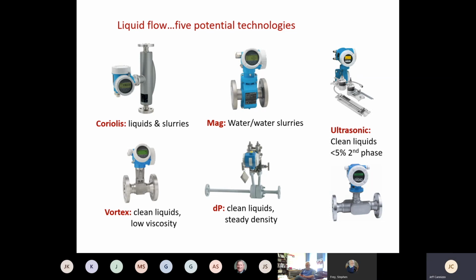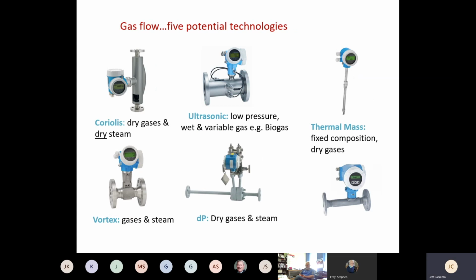Endress+Hauser does not manufacture the primary flow elements. Most of the representatives have relationships with other manufacturers. We have a relationship with Wyatt Engineering for orifice and Venturi meters. We have other relationships for pitot tubes, so we can still provide the complete solution. And then on the gas side, of course, Coriolis meters, ultrasonic meters. We have for gas. We're going to talk about a brand new one today a little bit. Thermal mass meters for clean gas. Vortex shedding meters for gases and steam. And differential flow meters, again, can handle dry gases and steam.